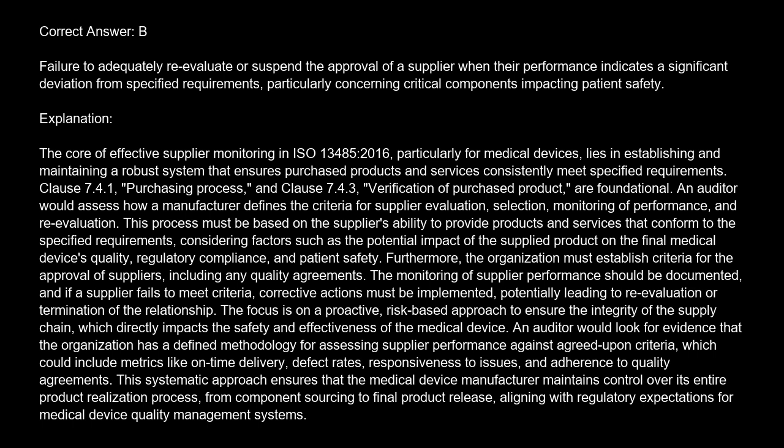The focus is on a proactive, risk-based approach to ensure the integrity of the supply chain, which directly impacts the safety and effectiveness of the medical device. An auditor would look for evidence that the organization has a defined methodology for assessing supplier performance against agreed-upon criteria, which could include metrics like on-time delivery, defect rates, responsiveness to issues, and adherence to quality agreements. This systematic approach ensures that the medical device manufacturer maintains control over its entire product realization process, from component sourcing to final product release, aligning with regulatory expectations for medical device quality management systems.